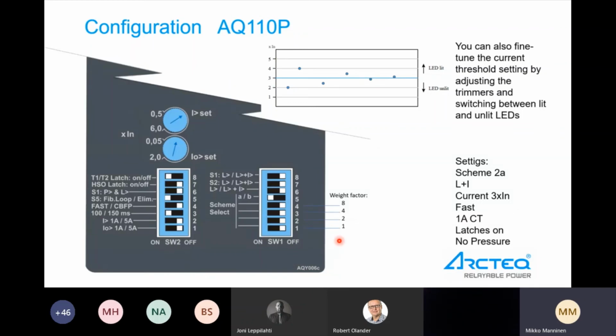When you know from the design that you have a special scheme, for example 4A or 4B, you can then just select here 4 and B. So this part is pretty easy. Then from the design, you can see that yes, we want to have light plus current to all of the outputs. So from these DIP switches, we can select S1, sensor 1. We can select light plus current, light plus current, light plus current, like this here.